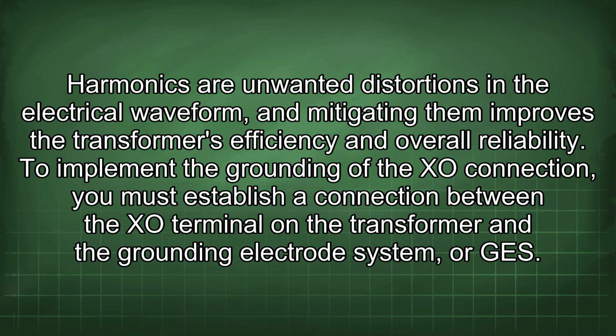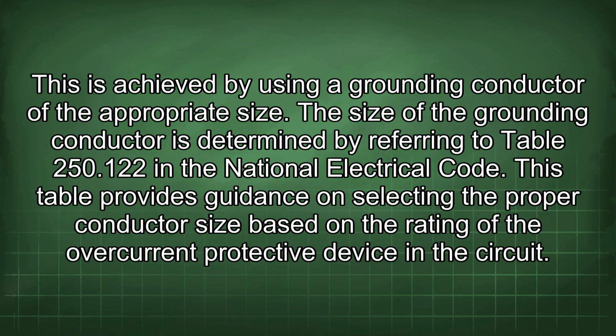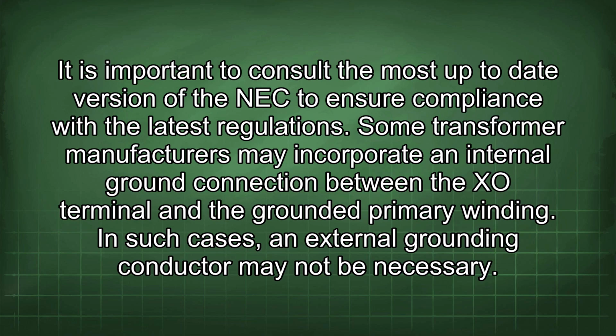To implement the grounding of the X0 connection, you must establish a connection between the X0 terminal on the transformer and the grounding electrode system, or GES. This is achieved by using a grounding conductor of the appropriate size. The size of the grounding conductor is determined by referring to Table 250.122 in the National Electrical Code. This table provides guidance on selecting the proper conductor size based on the rating of the overcurrent protective device in the circuit. It is important to consult the most up-to-date version of the NEC to ensure compliance with the latest regulations.